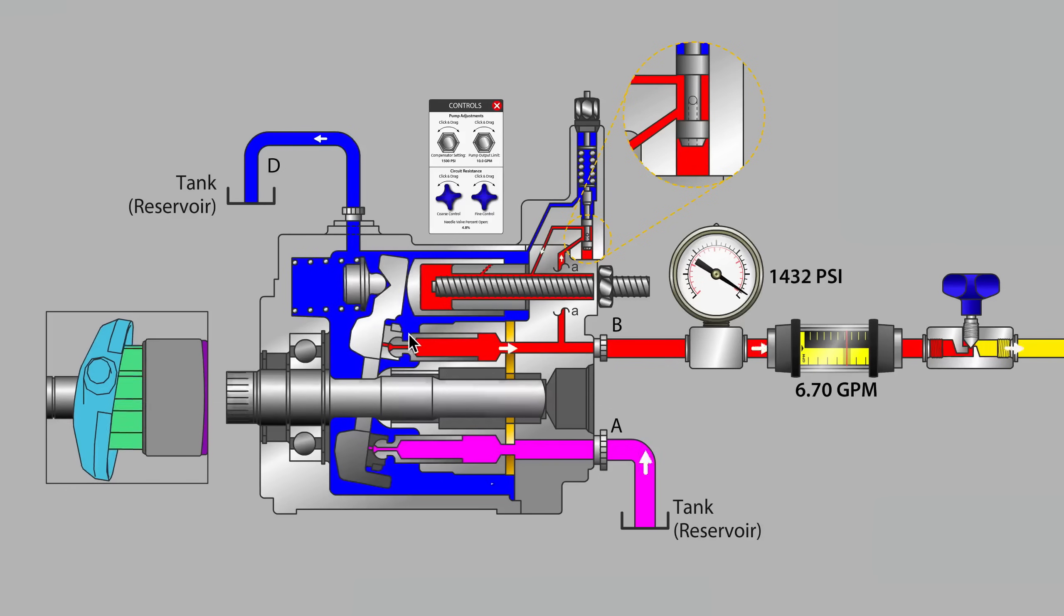All of those clearances, and in some languages when you read the notes for a piston pump they literally refer to this fluid in a word that translates to leakage oil. We're not necessarily talking about bad leakage but it is internal leakage between components that have a clearance. That fluid together with controller exhaust comes together and all of that is present on the case drain line.